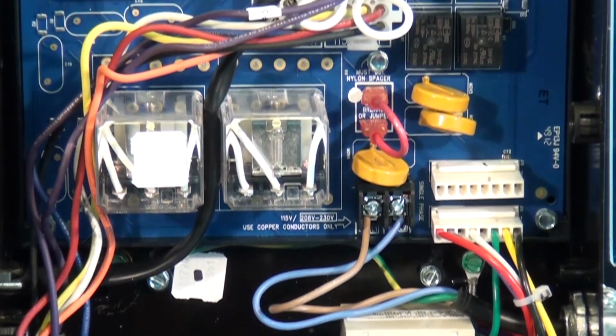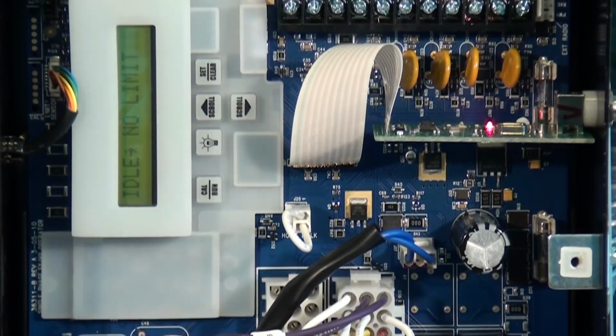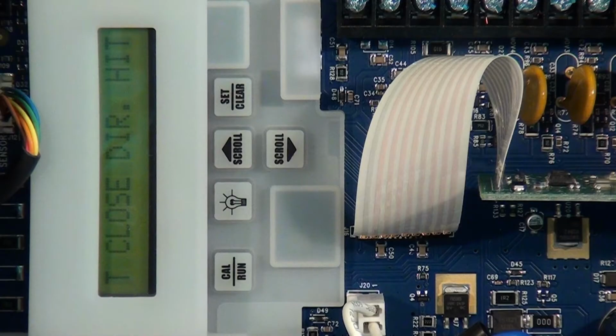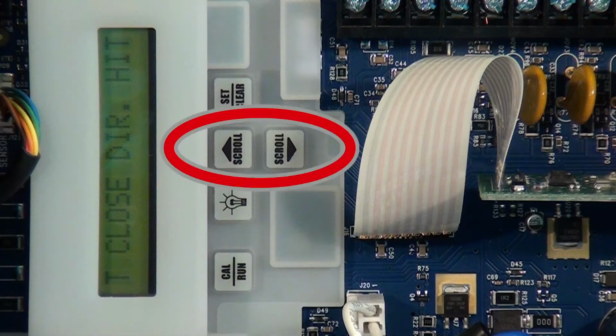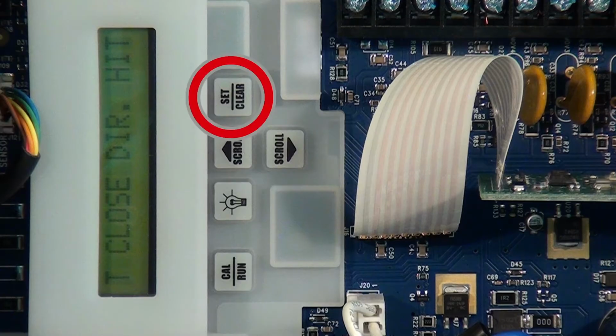First, let's get familiar with the circuit board configuration. Beside the LCD display, you will notice the calibration run key, which will be used to toggle between calibration or programming mode and run mode. Above that is the backlight key for illuminating the display in low light environments. Next are the up and down scroll keys. We will use these to scroll through menu options. Above those is the set clear key for accepting entries.